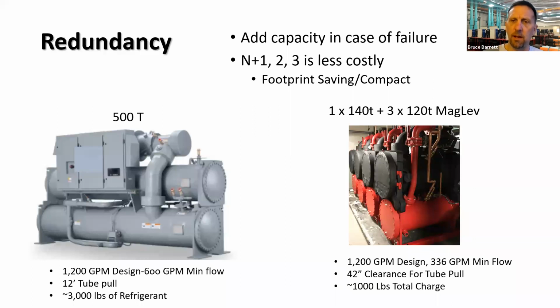Turn down, once again, a modular mag bearing, each compressor, let's say that 120-ton compressor can unload to about 20 tons of capacity. So 20-ish tons versus a minimum turn down on the single set of shells of about 200 tons of capacity or 150 tons of capacity. It's a dramatic difference. Also, the flow changes, minimum flow requirements. We can unload to 1 module's worth of flow, 336 GPM using the 10-degree delta T rule of thumb versus 600 minimum flow GPM. Pump energy is real. That turn down is important both on the compressor side and the pump saving side.